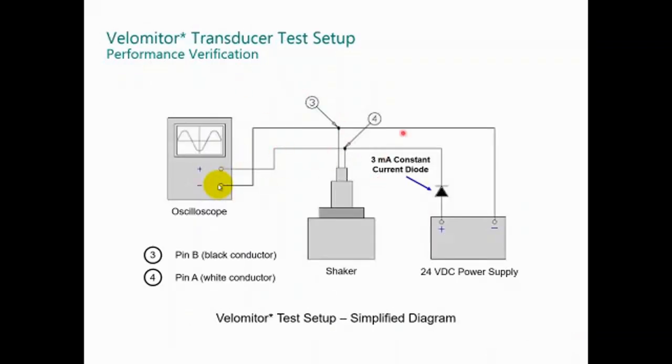For testing the Velomitor using external power supply, don't forget the 3 milliamp constant current diode to protect the transducer. It's mandatory to do that. If you're using the monitor, you don't need the constant current diode because it's included into the monitor.